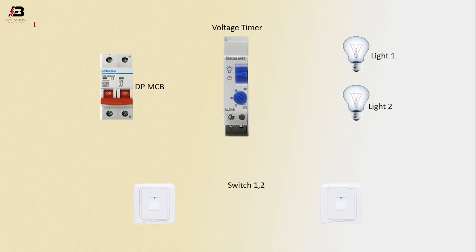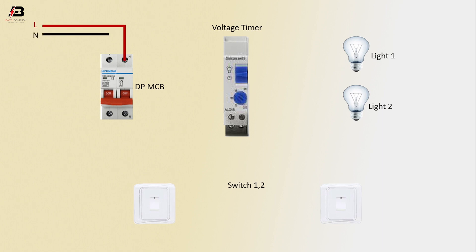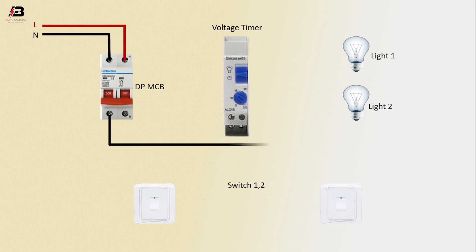Phase connection input to DPMCB. Neutral connection input to DPMCB. Neutral connection from DPMCB to connect light 1 and light 2. Neutral connection input to voltage timer.